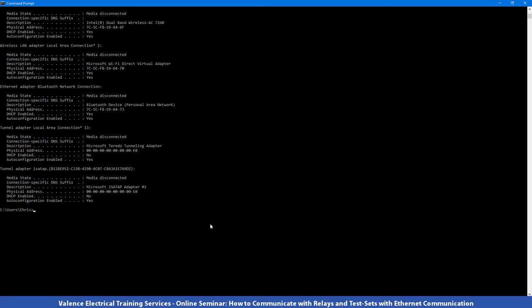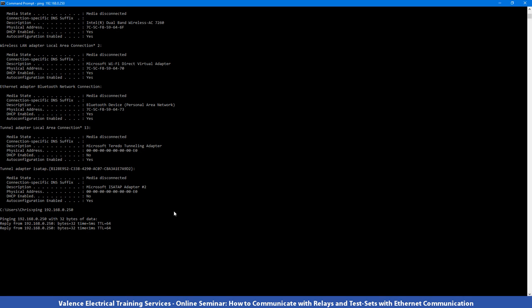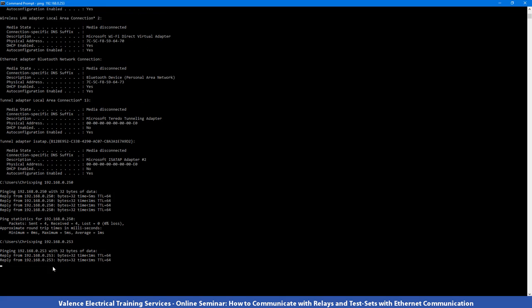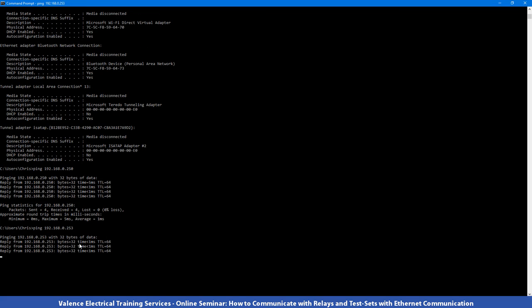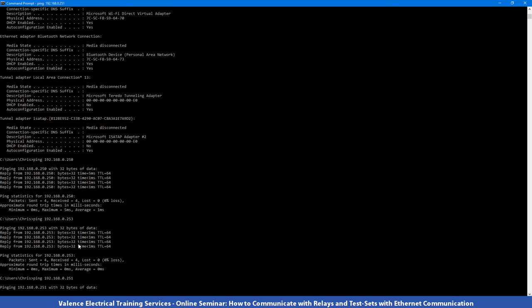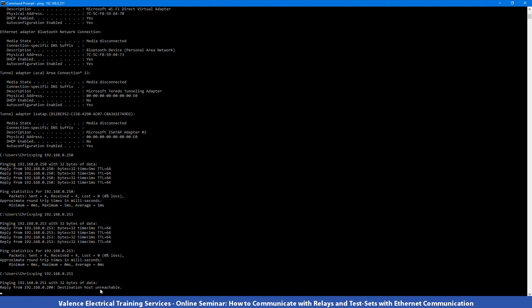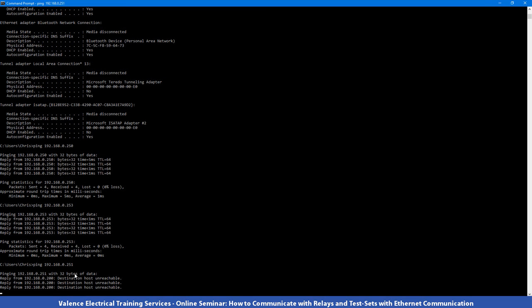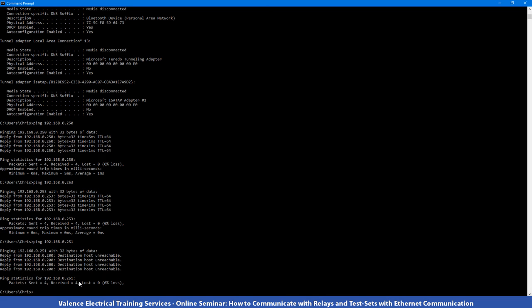I can also test the communication channel between devices by using the ping commands. So ping 192.168.0.250 and you can see that information is going out to the device and coming back and it's taking less than 5 milliseconds each way. I can ping the other device as well and go ping 192.168.0.253 and information is going backwards and forwards. If there wasn't communication, I can go ping 192.168.0.251. And if you don't see something come back right away, you know that there's something wrong and eventually it'll say something like destination host unreachable, which means that you do not have a physical connection between the two devices or the addressing is wrong.